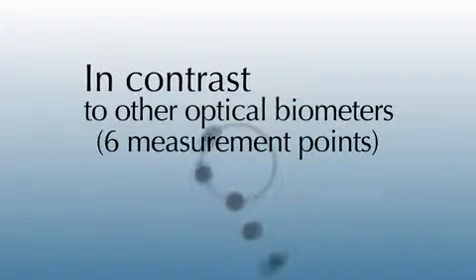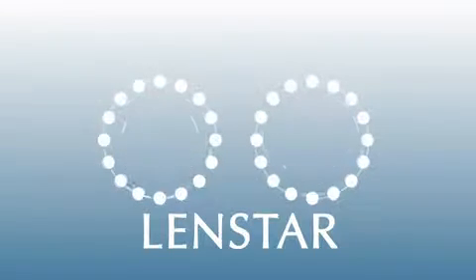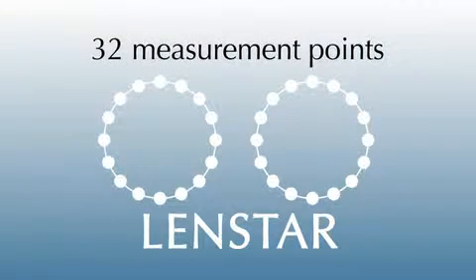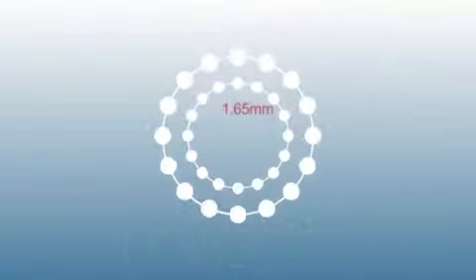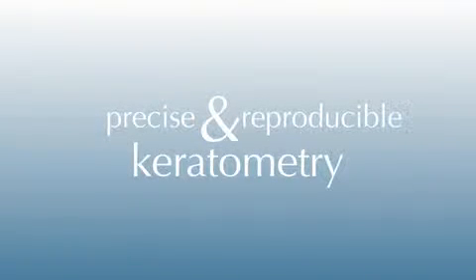In contrast to the other optical biometer, which utilizes six measurement points on one concentric ring at about 2.5 millimeters, LENSTAR utilizes 32 measurement points placed on two concentric rings of 16 points each at 1.65 millimeters and 2.3 millimeters, to ensure precise and extremely reproducible keratometry.